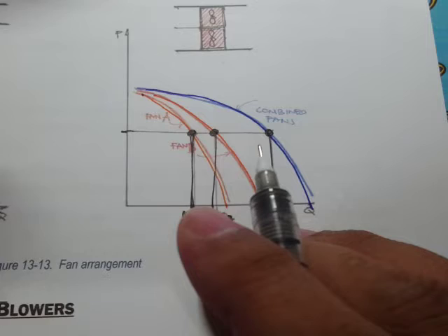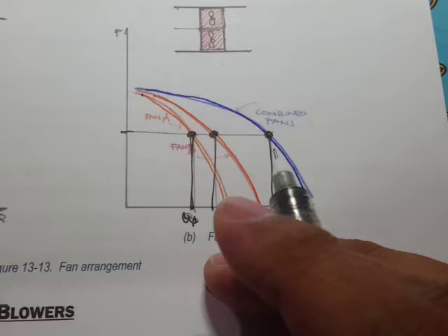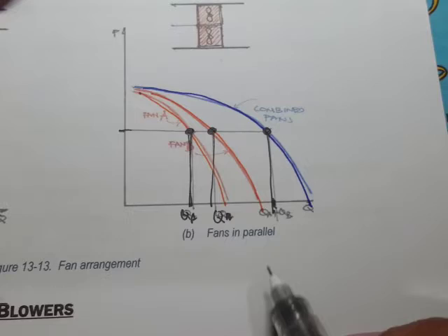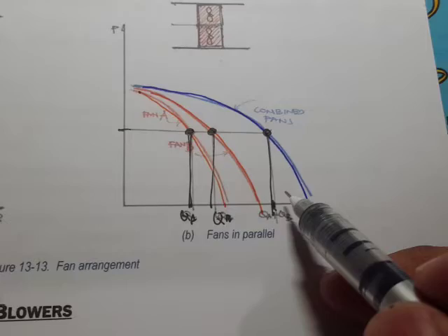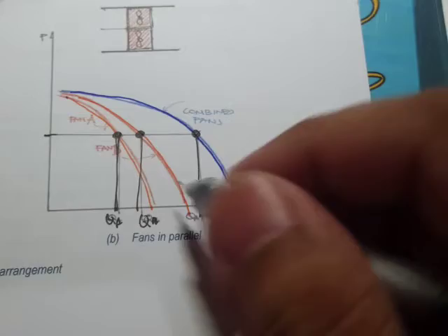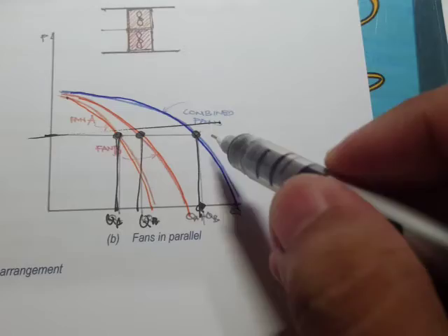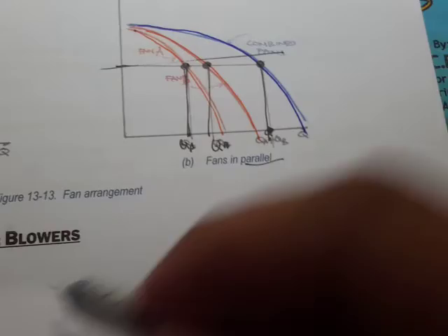In summary: if you want to increase pressure without changing flow rate, connect the fans in series. If you want to increase flow rate without changing static pressure, connect the fans in parallel.